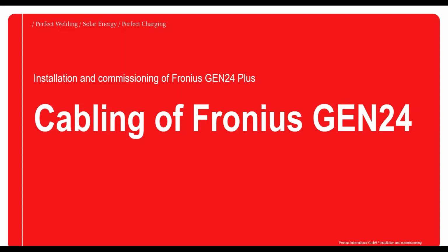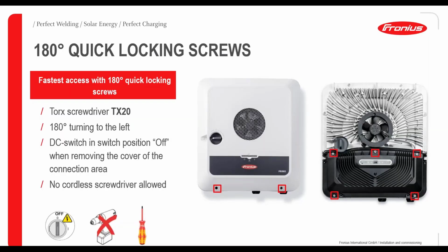Let's take a closer look now at the cabling of the Fronius GEN24 inverter. Before we get to the cabling, of course, we need to take off the cover. And this is done very fast with 180 degree quick locking screws. This means, first of all, please don't use any kind of power drills, otherwise the screws or the terminals will be destroyed. But the more important thing is we can do it very fast. Just with half a turn of the screwdriver, we can open the front cover with these two screws on the bottom. Please also make sure to disconnect the DC disconnector switch to the off position, and after that we can take off the whole front cover.